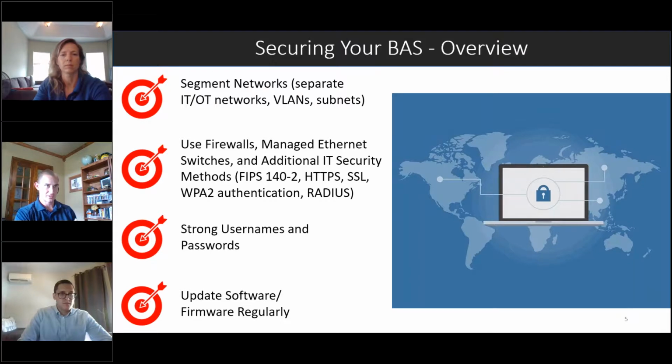What we can do with the managed switches is tell it that if you unplug that device and the MAC address of the device that's plugged in changes, then it'll deny it access into the system. Or if the port's open and nothing's plugged in, then it can say that port is just shut off, there's nothing on it. So if someone did try to plug in, it would just block them from communicating. Yep.